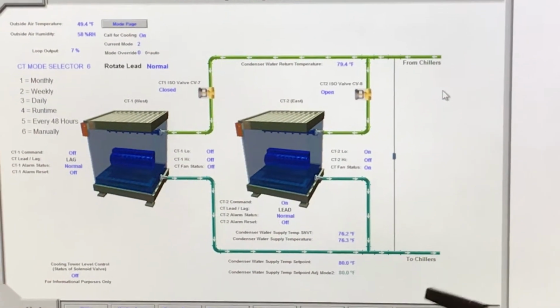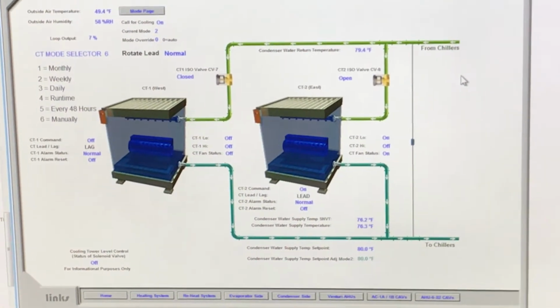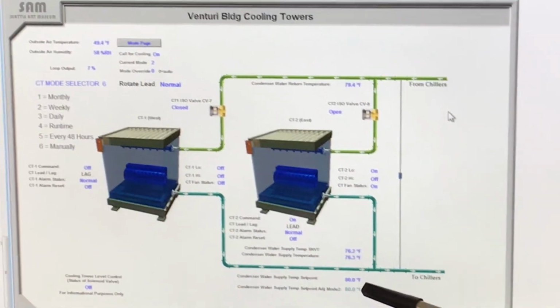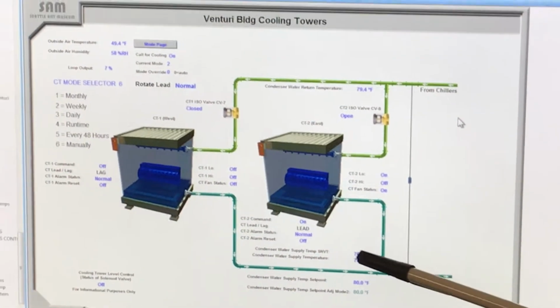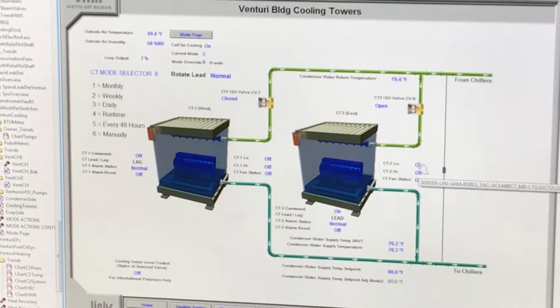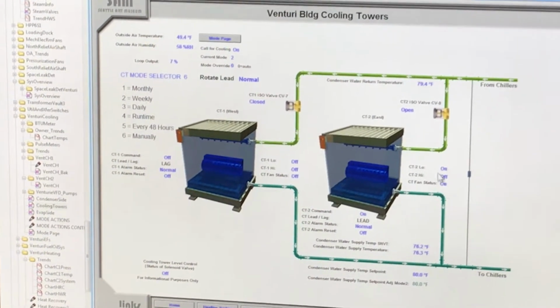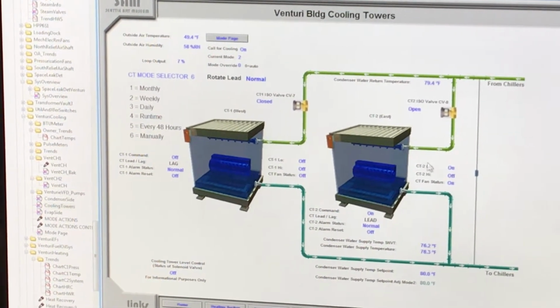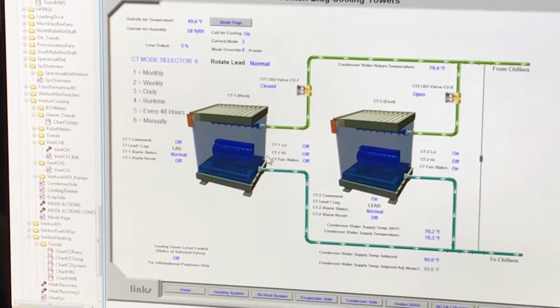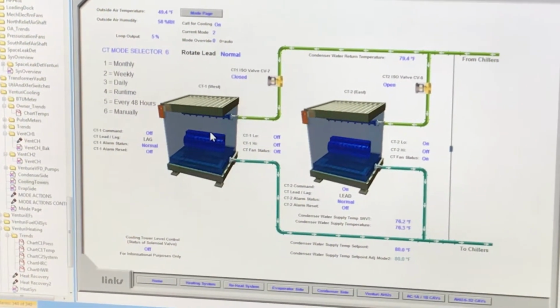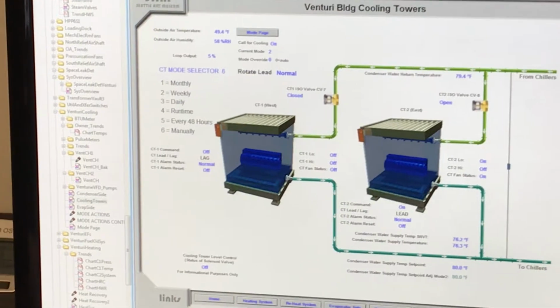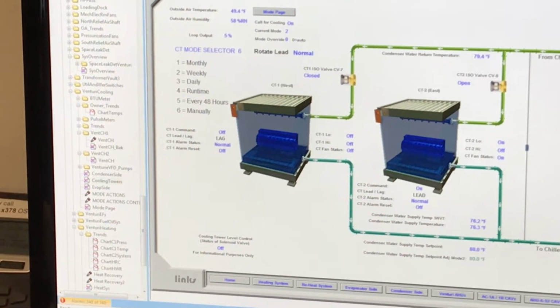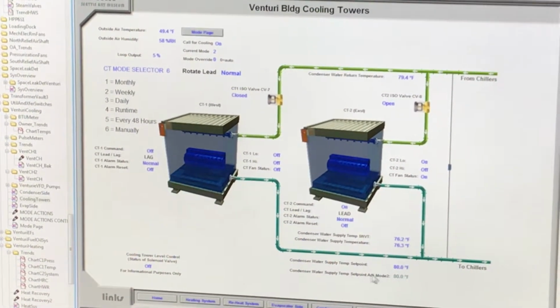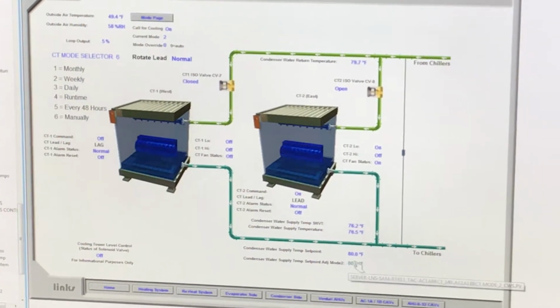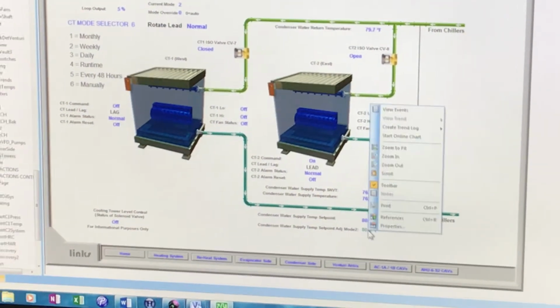What would happen if this temperature goes over 80? Then it would start to ramp up, and this would go to high. Then they'll go to high and low, and then high and high. The set point is determined by the program, except in mode 2. In mode 2, it's adjustable down here.